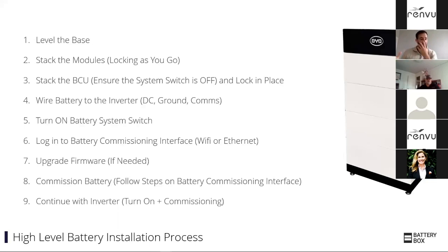Then once all wired up, you're going to turn on the battery system switch. It's a breaker on the other side of the battery. You're going to log into the battery. Easiest way to do that is via Wi-Fi, but there are 2 routes, and we'll talk about that in a second. You can upgrade the firmware if needed. You're going to commission the battery. So essentially, you're just going to tell it how many modules it has in a stack and which inverter it works with. And then you're going to continue on to the inverter, turning the inverter on and commissioning it.